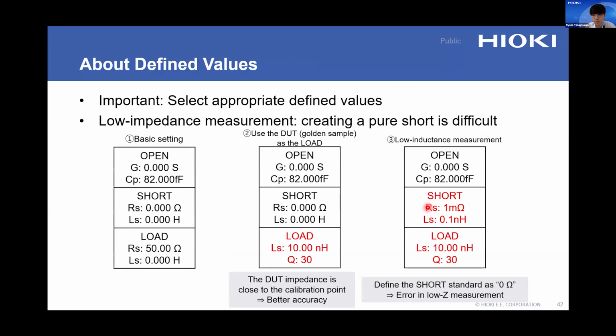Okay, finally, I will explain a slightly more advanced point, the defined value used for calibration. For example, when measuring the calibration kit, the defined values are as shown in figure 1 here. The open is 0 Siemens, the short is 0 ohm, and the load is 50 ohm. However, accuracy is best around the calibration point. Therefore, if you are repeatedly measuring the same type of DUT on the production line, it can be effective to use a golden sample of the DUT as the load standard.